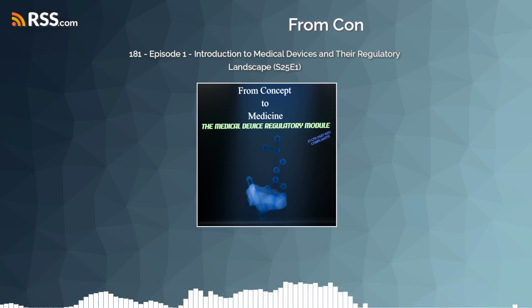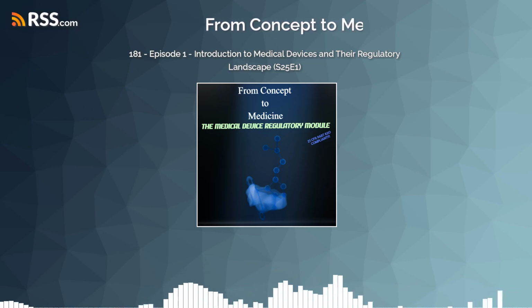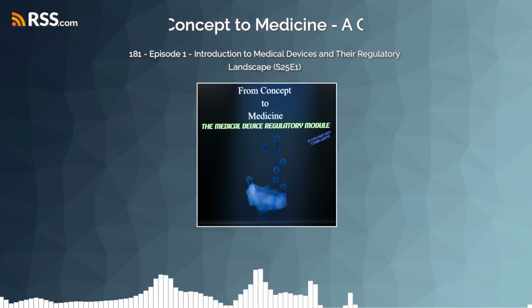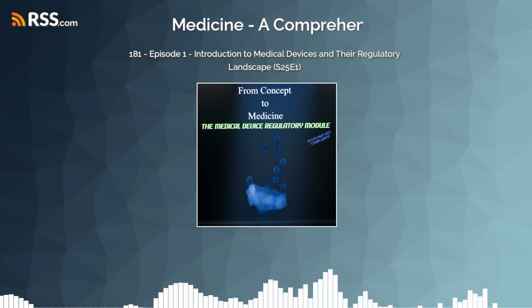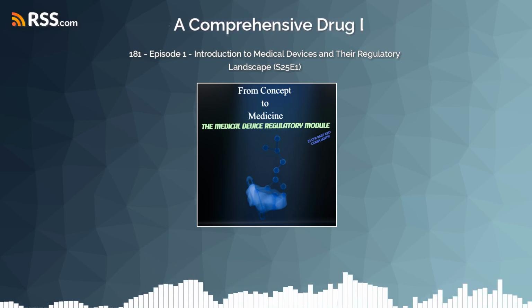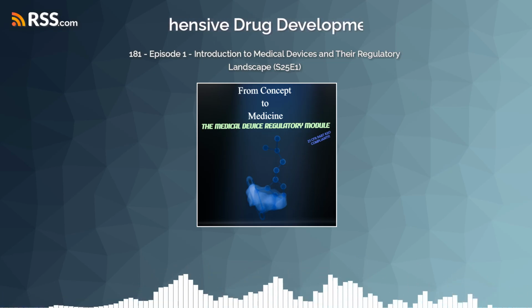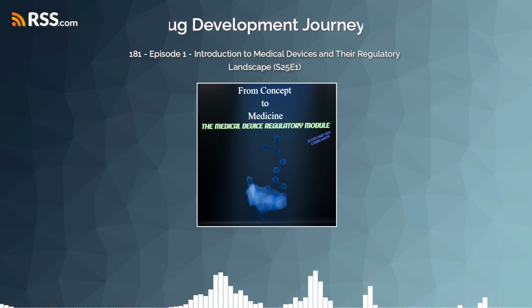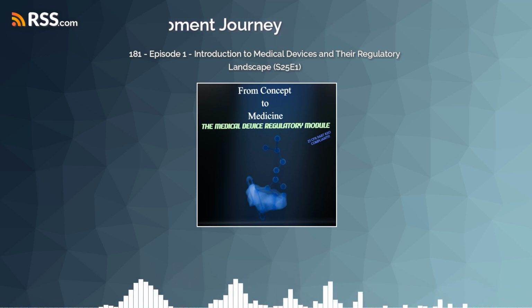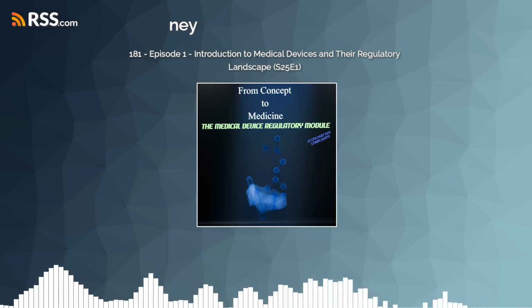Then there's design validation. This ensures that the final finished device actually meets the user's needs and its intended uses. So asking, did we design the right device? This often involves testing under actual or simulated use conditions and very often includes data from clinical trials. Right, validation. Did we design the right thing?